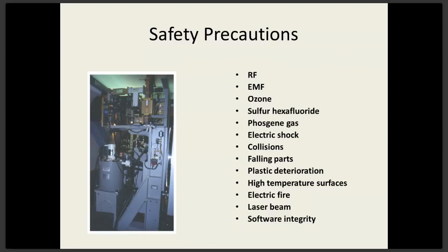Laser beam is not a terrible hazard. These are quarter milliwatt lasers. They really won't do any harm, but they still come with a warning not to stare at the laser beam directly. And software integrity is always, always, always a problem. Is this software communicating correctly? Is it really telling the multi-leaf collimator leaves where to move correctly? So these are just some of the precautions, and I'm sure you can think of more things that are hazardous in the room that we deal with on a day-to-day basis.